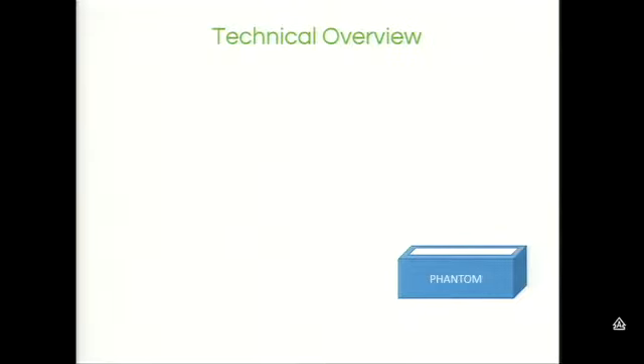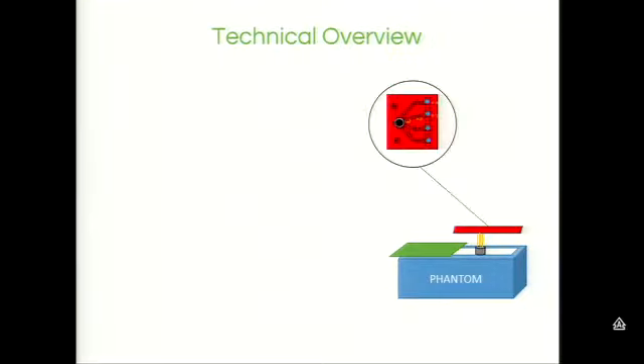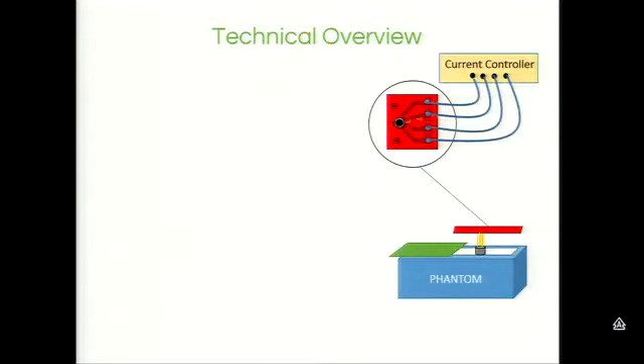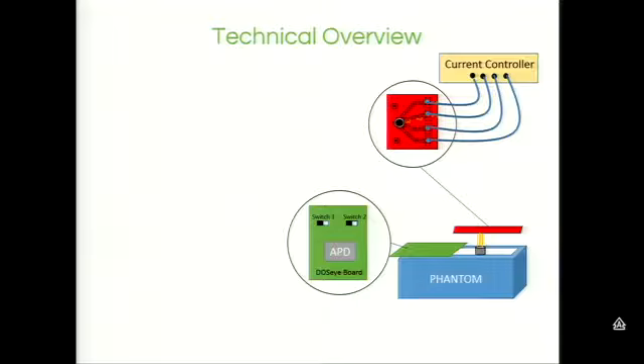So how do we use it? We start off with a phantom, which simulates human tissue. It's a silicone block. We put our detector and source on top of it. Our source is a vertical cavity surface emitting laser, or VCSEL for short, blocked out in the middle, and this is the PCB to run it. It's connected to a current controller, which puts current through the VCSEL and shoots light out. Our APD, or avalanche photodiode, is our detector, which also runs on a PCB. That requires high voltage, so we have voltage conversion from the wall into the board.